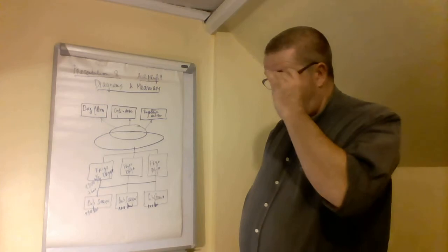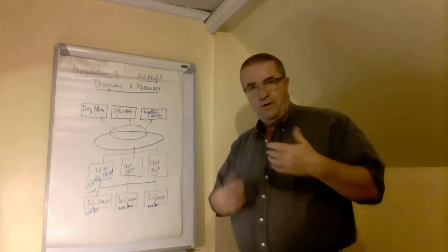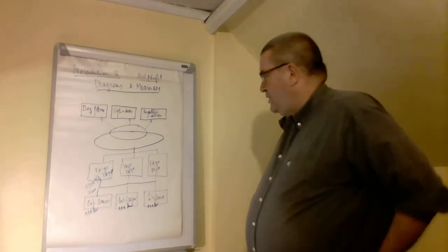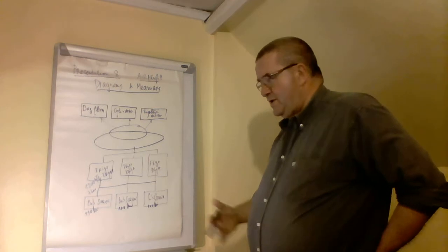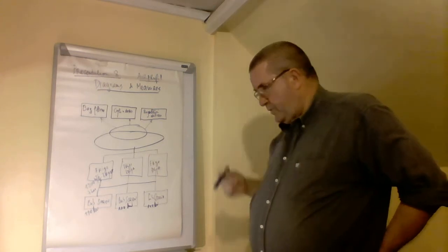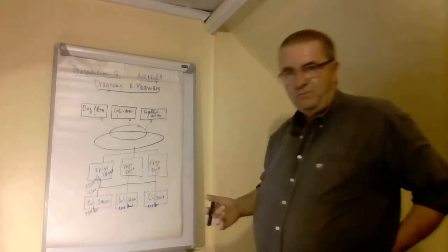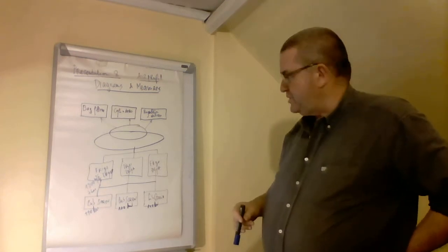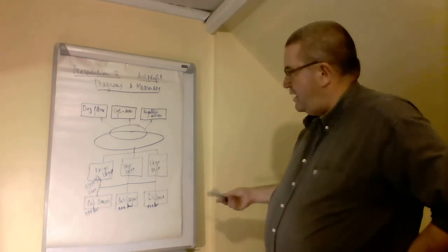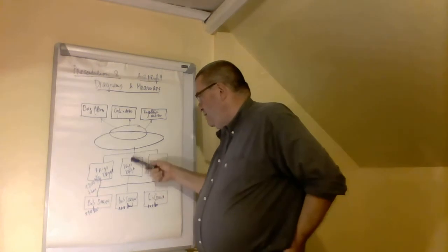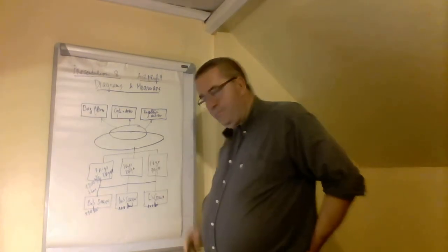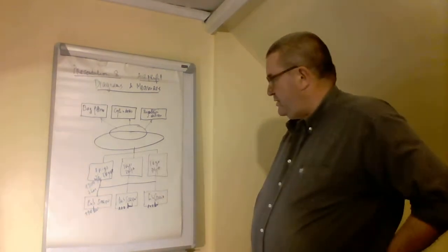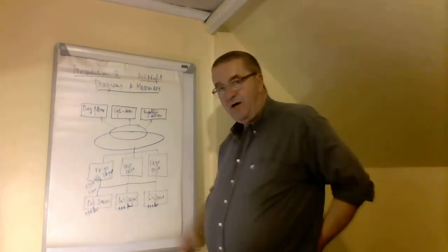And this is the order of magnitude, a rough estimate of the lowest non-availability that you may have. It's difficult to go strictly under 2% of the time. During this time you will maybe send some water into the pipe work because your dryer is out of work.